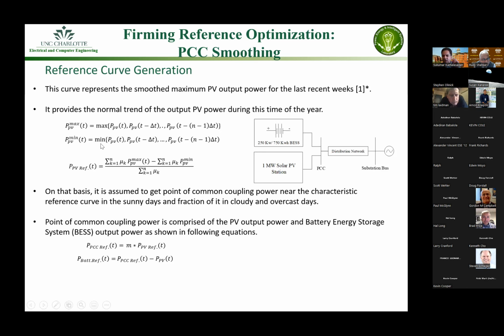How we calculate this reference is by looking at the past 7 days of historical value. Like I said, we are not doing any forecast, only precast values, looking into previous values of the photovoltaics to find the minimum and maximum value. Based on that minimum and maximum, we create a reference value within that range, and the change in that reference value is associated with the reference for the power coming from the point of common coupling.